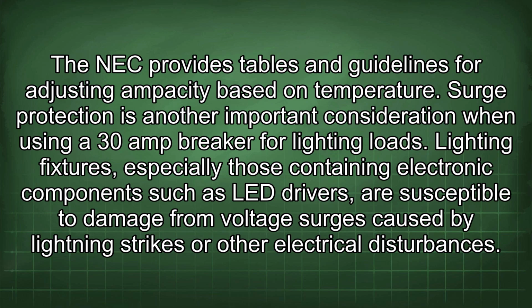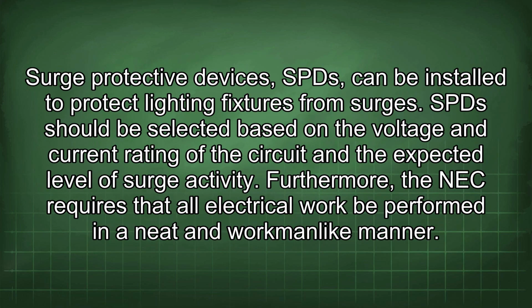Surge protection is another important consideration when using a 30-amp breaker for lighting loads. Lighting fixtures, especially those containing electronic components such as LED drivers, are susceptible to damage from voltage surges caused by lightning strikes or other electrical disturbances. Surge protective devices, SPDs, can be installed to protect lighting fixtures from surges. SPDs should be selected based on the voltage and current rating of the circuit and the expected level of surge activity.